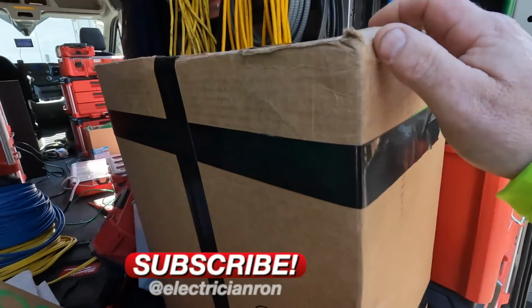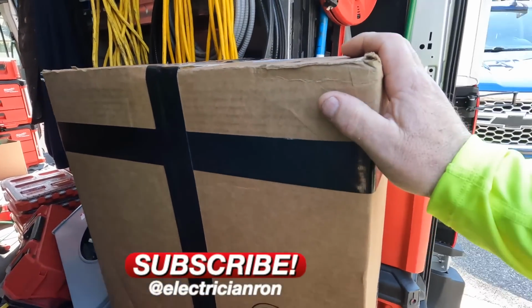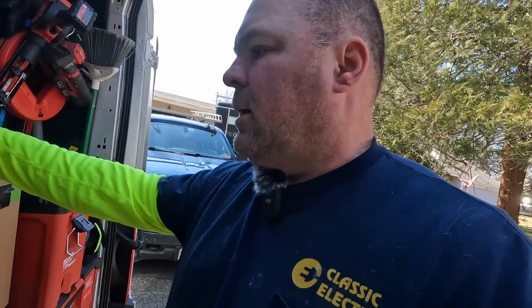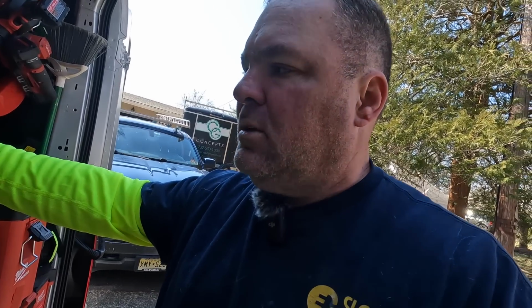All right guys, it's after lunch now. Here's the transfer switch that we're going to be putting in right here. It's a Kohler 200 amp service rated entrance switch, and it's basically going to go back to where the other transfer switch was. This enclosure is a little bit larger, so I need to do two things. I want to come out of the bottom of the transfer switch with the load going to my electrical panel on the inside. But I also need to make sure that the generator set that comes through the wall comes into the back of the enclosure and lines up with that.